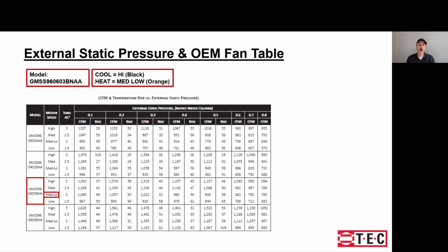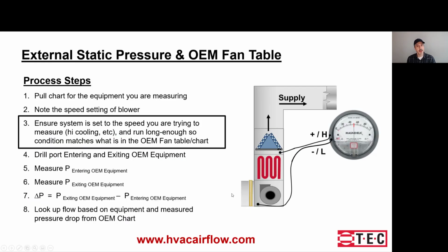Okay, so you saw Steve got the model number and noted the blower speed settings. And with that information, using Google or the manual, we can make sure that we have the right table or chart where we're going to convert that external static pressure we're about to read in inches of H2O, or inches water column, so that we can look up the right flow reading. With that in hand, it's reasonable to go to the next steps.